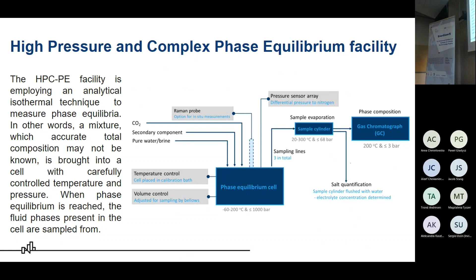And let's start with my work. I started with temperature calibration. We wanted to use 2 SPRT sensors, but during the calibration, unfortunately, one sensor broke, so we had to replace it with PT100. It has a less accuracy, 12 millikelvins against 1 millikelvin, but it's still a good accuracy for our project. How does this sensor measure the temperature?